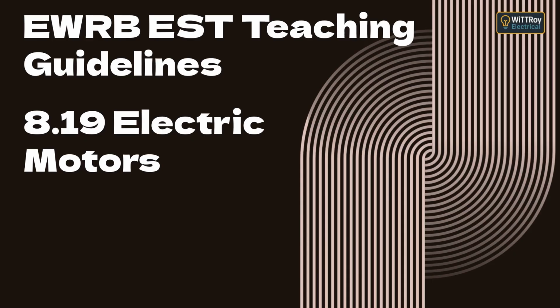Topic H. Direction of rotation. Now let's move to Topic H. Direction of rotation. In a three-phase motor, the direction of rotation depends on the phase sequence of the supply. If you swap any two of the three-phase conductors, the motor will rotate in the opposite direction.